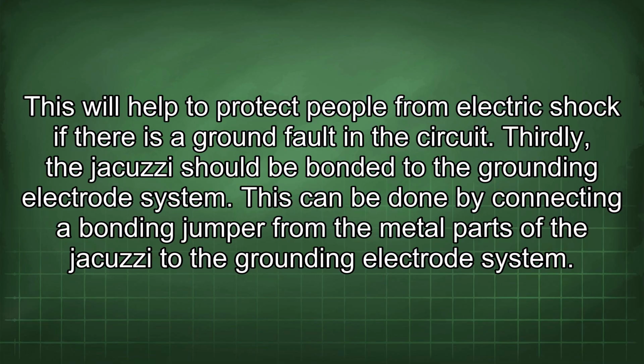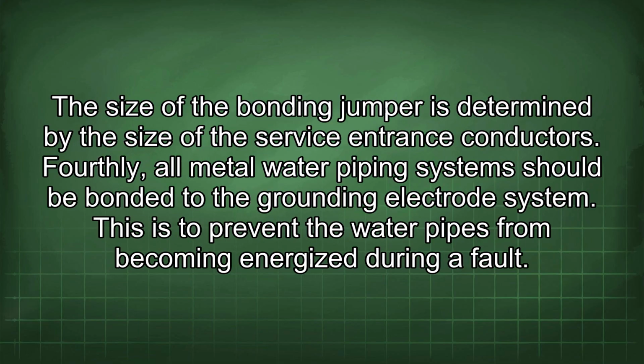Thirdly, the jacuzzi should be bonded to the grounding electrode system. This can be done by connecting a bonding jumper from the metal parts of the jacuzzi to the grounding electrode system. The size of the bonding jumper is determined by the size of the service entrance conductors.